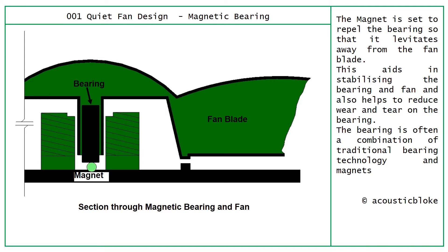The last bearing system is the magnetic bearing. A magnet is set in the bearing to repel it so that it levitates away from the fan system or motor, aiding stability and reducing wear and tear. The bearing is often a combination of traditional bearing technology and magnets; in this example the magnet is placed at the bottom to help centre the bearing as the fan spins. This technology is all about controlling wear and tear, stopping the fan from going out of balance, and reducing the creation of noise.